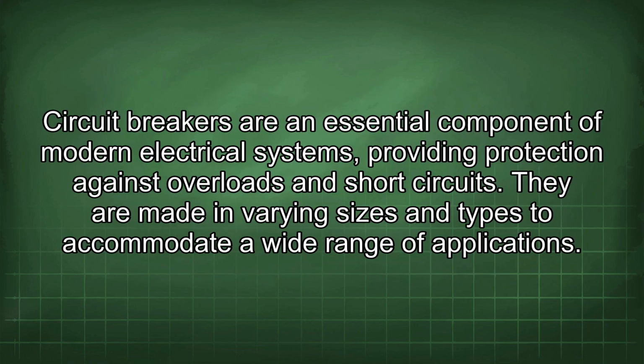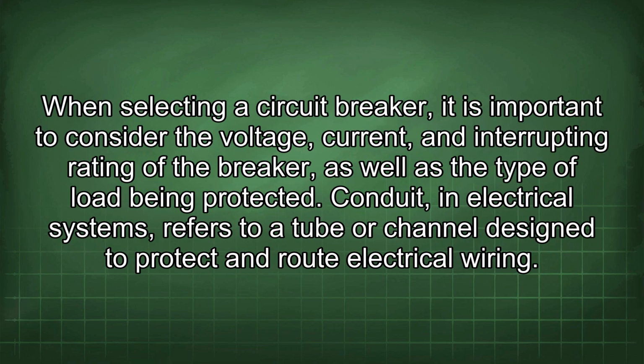Circuit breakers are an essential component of modern electrical systems, providing protection against overloads and short circuits. They are made in varying sizes and types to accommodate a wide range of applications. When selecting a circuit breaker, it is important to consider the voltage, current, and interrupting rating of the breaker, as well as the type of load being protected.